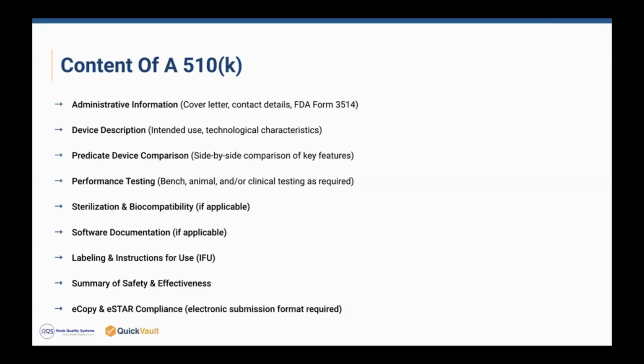Next, we'll have some performance testing. This is where you will include information around your bench testing. So any internal testing you've done for your device, any animal testing, any external testing, like your biocompatibility, electrical safety, things like that, as well as any clinical testing. For 510(k)s, it's not always required that you do clinical testing, but for some devices like diagnostic devices and wearable monitoring devices, the majority of those will require clinical testing to be included with your 510(k).